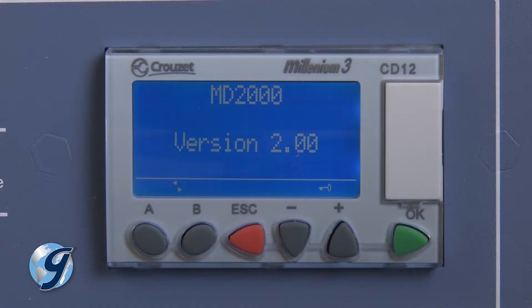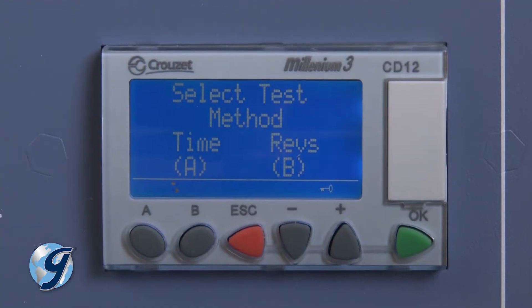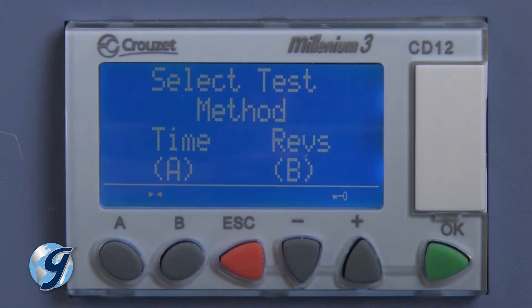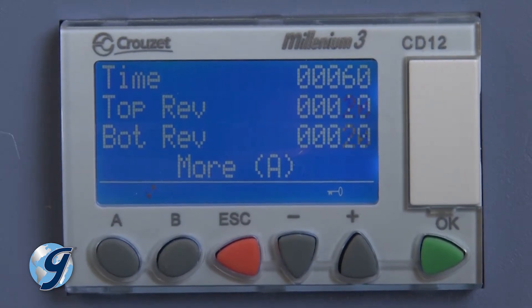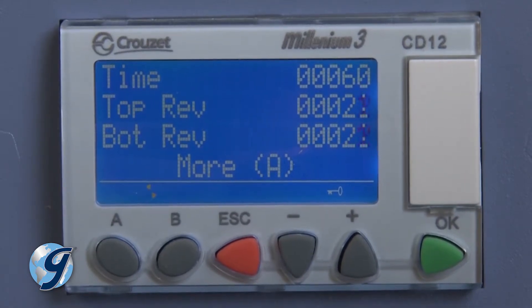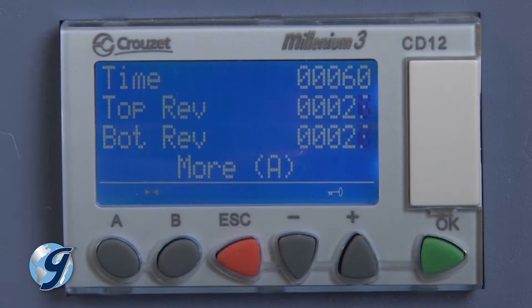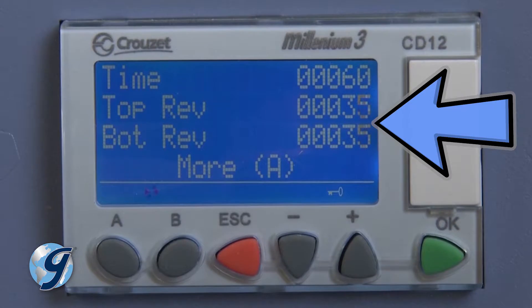The electronic controller of the MD-2000 allows the test duration to be controlled either by elapsed time or number of jar revolutions. In the time mode, the test will continue until the timer reaches zero. Test jar revolutions are displayed on the counter, but the revolutions counter does not control the test.